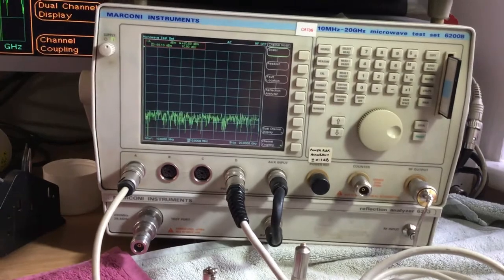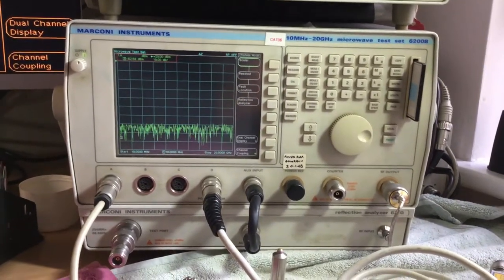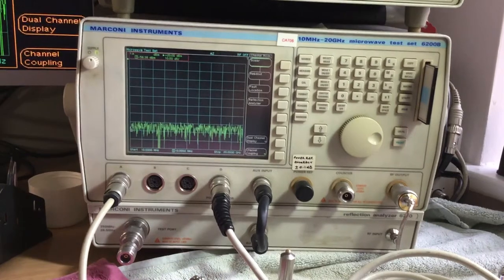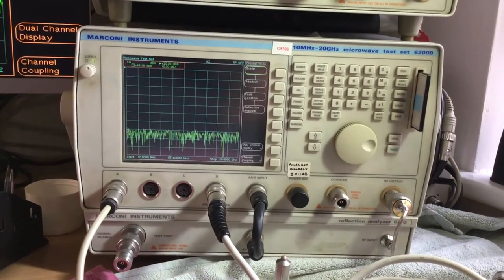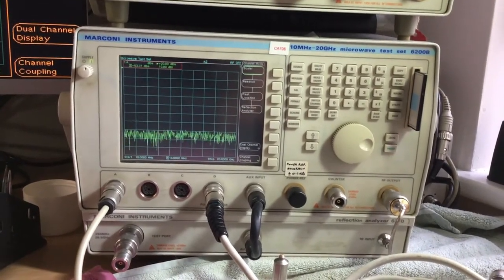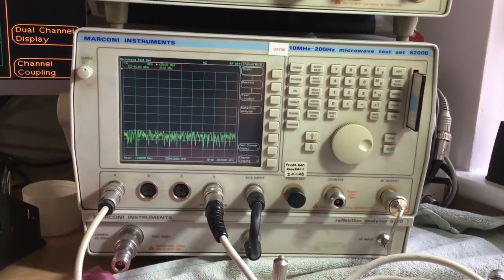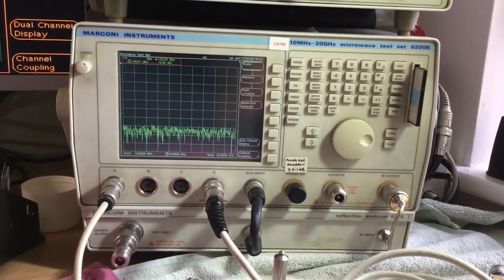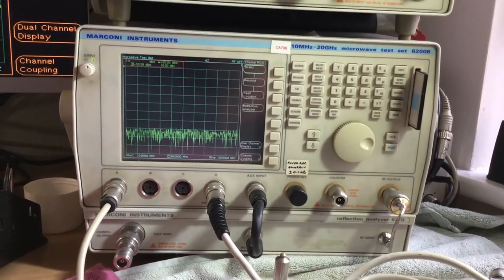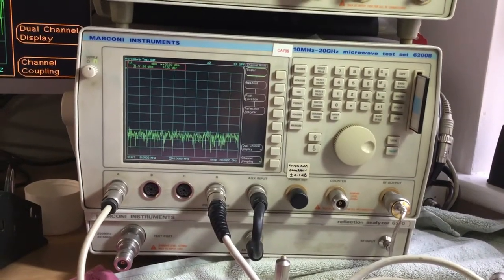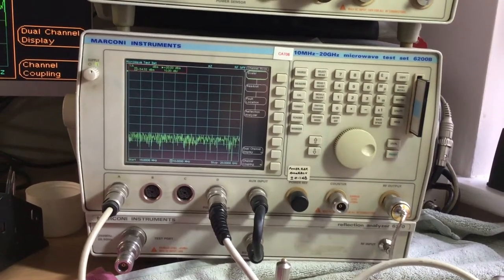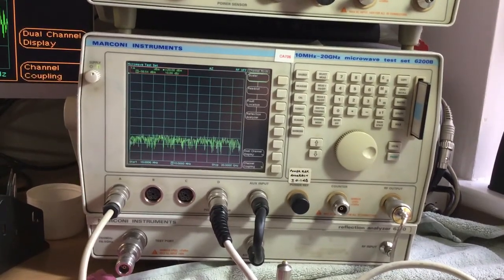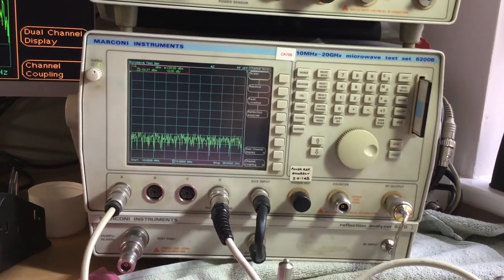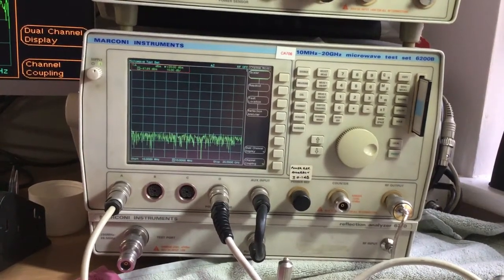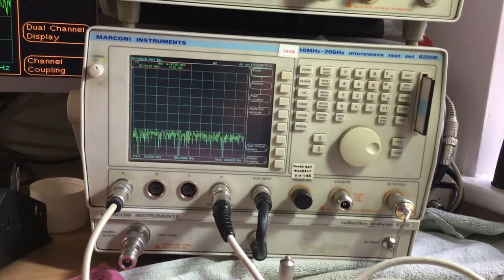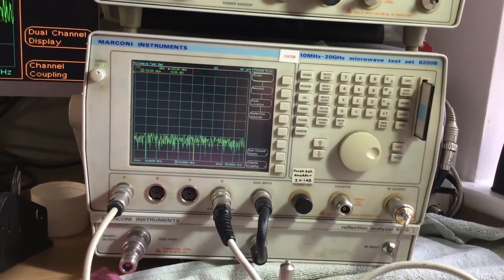This is a video about calibration of microwave radio test sets. This model in particular is a Marconi microwave radio test set 6200B. It also has at the bottom the tray added for S11, S21, 2 port parameters testing, which is the 6210 reflection analyzer or vector network analyzer add-on underneath, which you'll see later, displays Smith chart, log graphs.